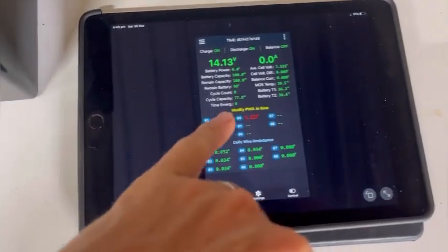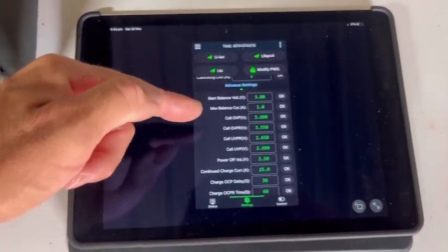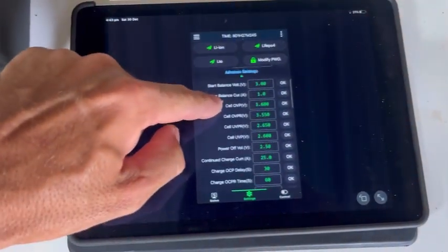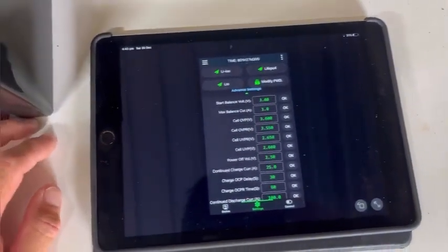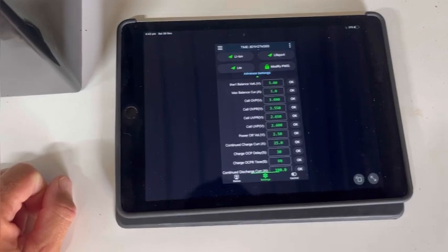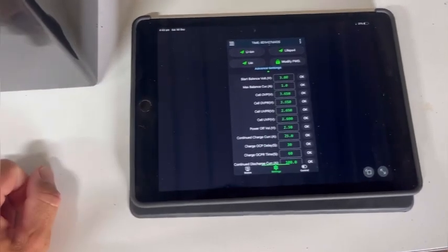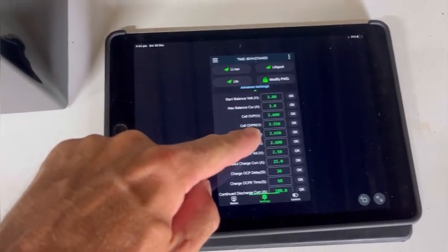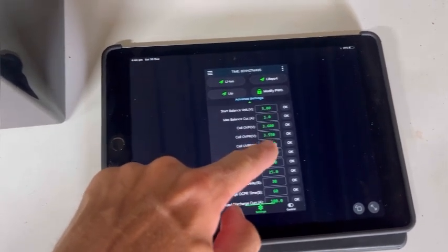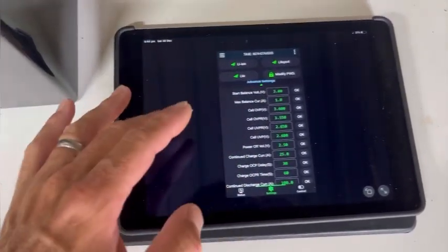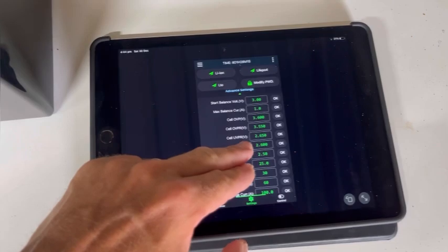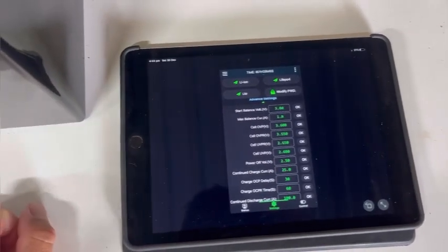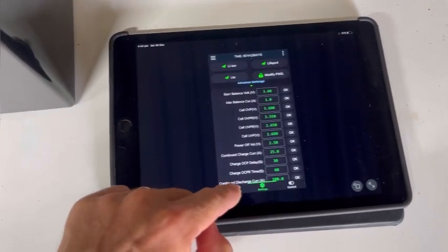Cycle capacity, 77.5 amp hours. The over-voltage protection for the cell is set to 3.6. I know these cells are 3.65 volts, but I always like to have that little bit of tolerance. I don't like to max them out. Comment if that's incorrect, but I always just like to leave a little bit of gap. The over-voltage protection recovery voltage is 3.55. I'm pretty happy with that. This was all pre-set, I haven't changed any of this. The under-voltage protection is 2.6, and the recovery is 2.65.